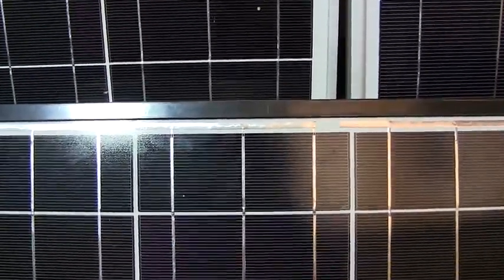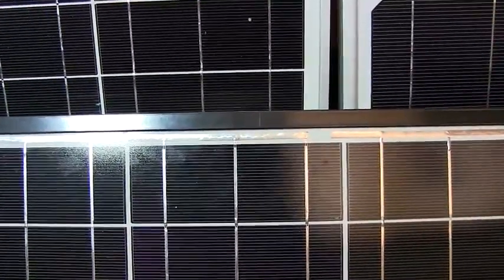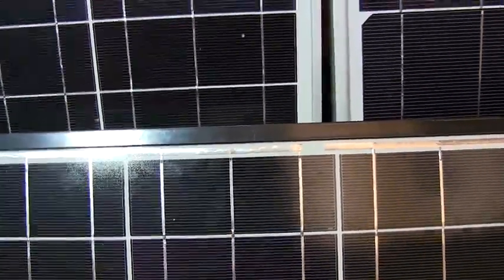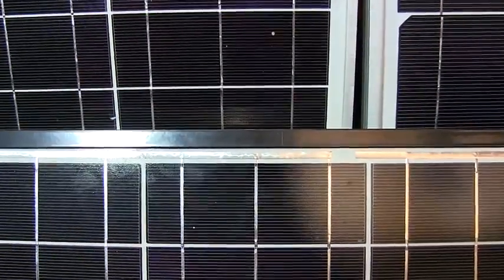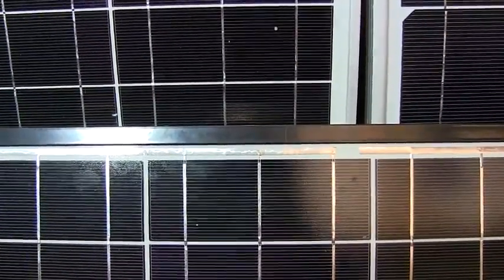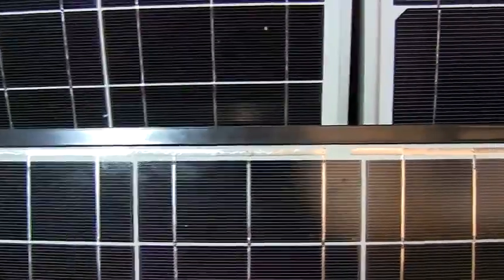Another point to note about these solar panels, potentially when you're going to link them up into, let's say, an MPPT grid tie inverter, you're going to be stringing potentially multiple panels together and you're going to have a high voltage going through these solar panels. Now the problem is that once you start having a high voltage going through your solar panels, and you have to check that your solar panels are rated to be able to do that, you then have the risk of things arcing over if there are metal connections that are too close to each other.